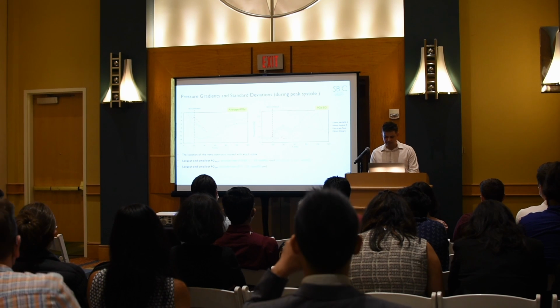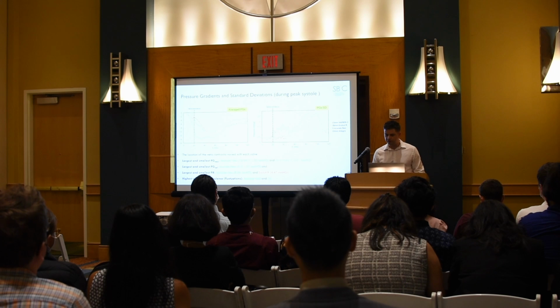The peak pressure gradient was highest with the Accurate Neo. At the recovery, which is at 20 millimeter, the smallest pressure gradient was obtained with the Allegra, and the largest pressure recovery was obtained with the Accurate Neo, and the smallest with the Evolut. And from the right figure, we can notice that the fluctuations of the standard deviations are higher with all the self-expanding valves because of the stent frame compared with the Sapien 3.